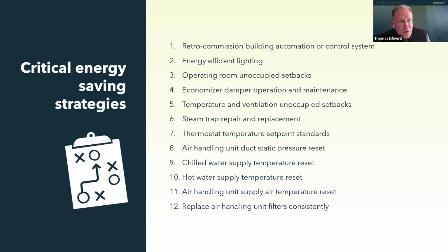Number 8 is a bit more complicated, or requires a little more knowledge: this idea of air handling unit static duct pressure reset. Let me simplify it. Many systems in our medical facilities can flow a different amount of air. Air is pushed down a duct, but it doesn't have to be pushed with the same pressure all the time. You can change the pressure based on the need of the occupants and the temperature.